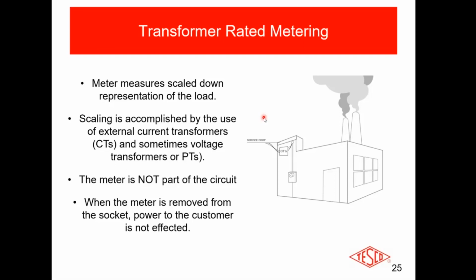Okay. Sometimes you also do that on the voltage, and you have PTs in there as well. The key here is the meter is not part of the circuit, because we certainly don't want to go out to a very large customer site and, when we pull the meter, interrupt their service. You can't do that. Typically, with commercial and industrial sites, as meter techs, the one thing we can't do, unless there is a scheduled shutdown, which sometimes takes an act of God with some of our customers, is shut it down. So the meter is not part of the circuit.